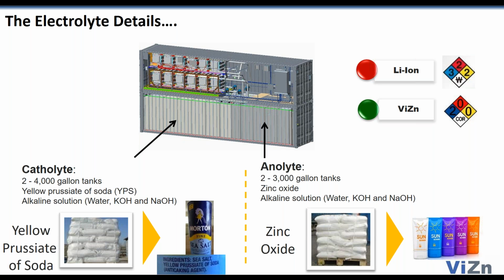Batteries are charged with the inverter. It's hooked up to an inverter, and simply by varying the voltage across the battery, if you get the voltage up above the open circuit voltage on the system, it will begin to charge. On our system, charging is accomplished by plating zinc out of the anolyte—the zinc oxide circulating in the anolyte is converted to zinc and grown on the anode plate. That's essentially how the system is charged. We can vary the voltage, which varies the rate at which the battery charges.